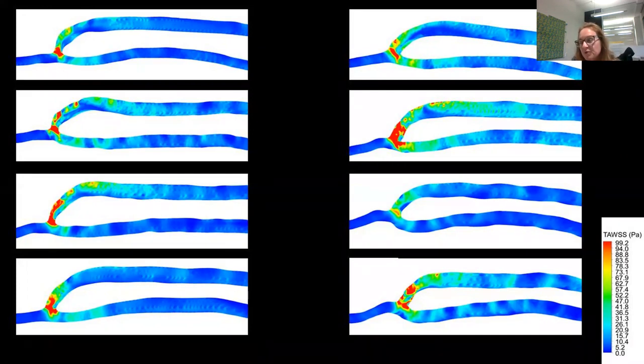Also how to get the waveform, because we want to get a very accurate patient-specific waveform, but we've got 2 inlets. So rather than using 2 pumps, we've just been trying to connect up the pump in a certain way so that we can get very close to the patient-specific profile.